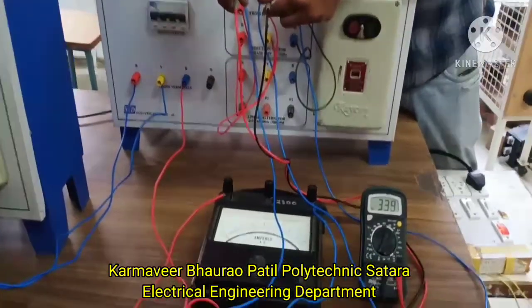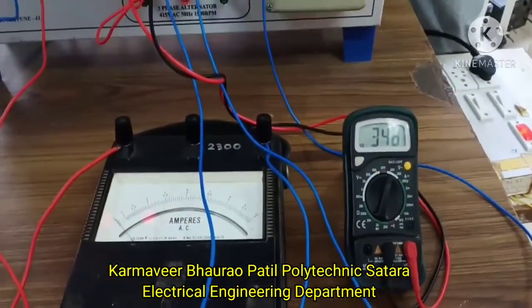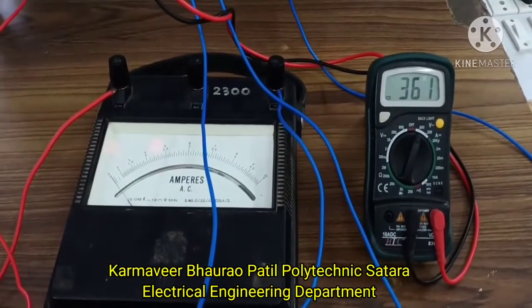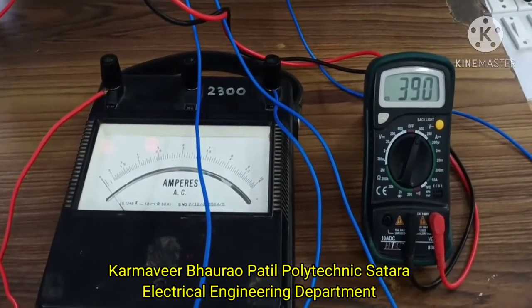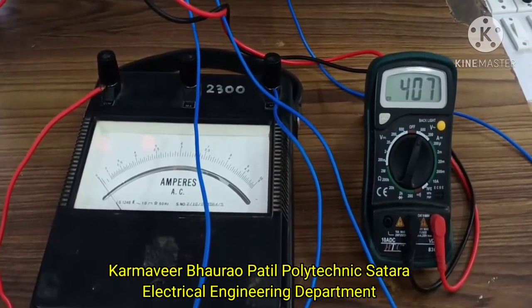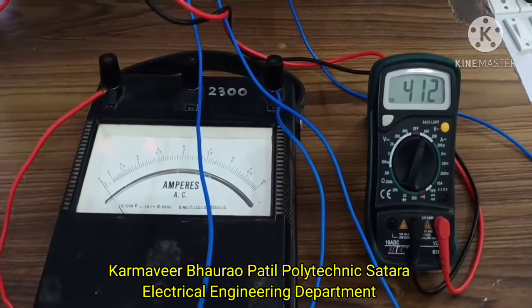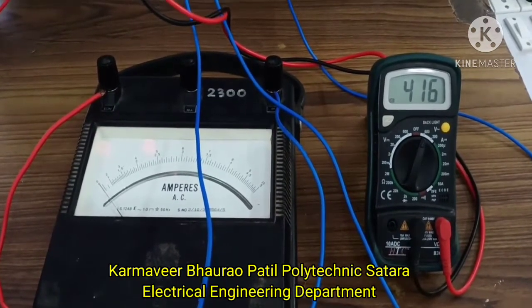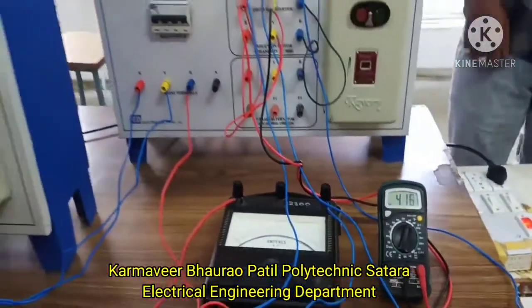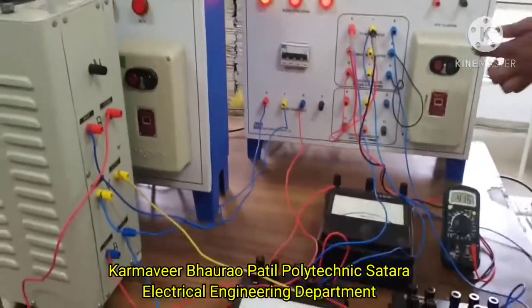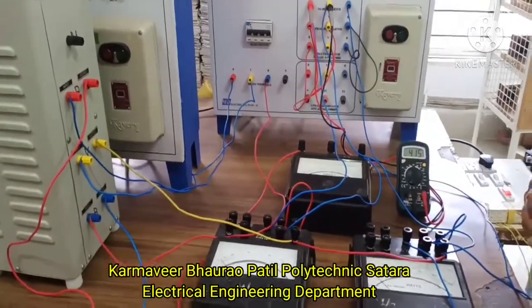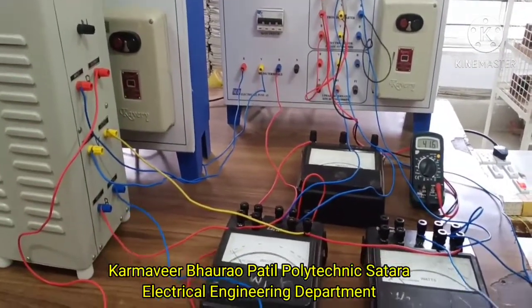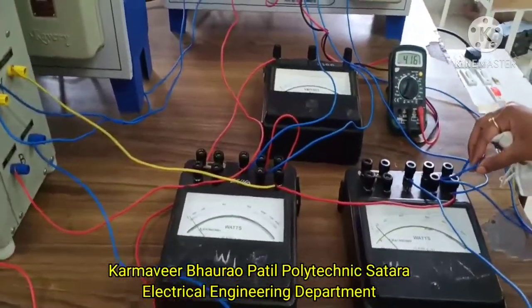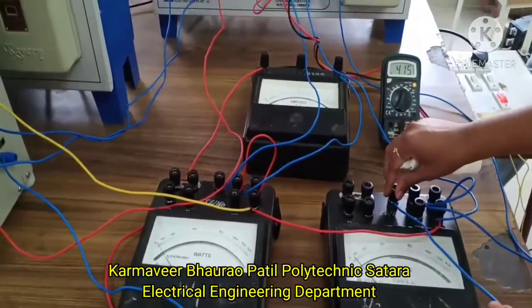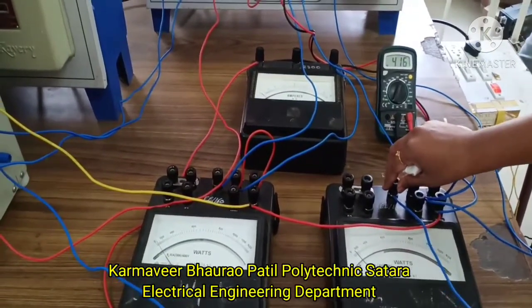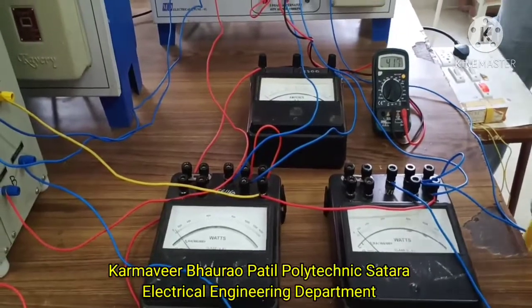We will adjust the rated voltage to 415 volt. Then for this no load test, we are getting a low power factor. Hence we just interchange the wattmeter connections, so that the M terminal is connected to the motor and the L terminal is connected to the auto transformer's output. Okay. Now we will perform the no load test.